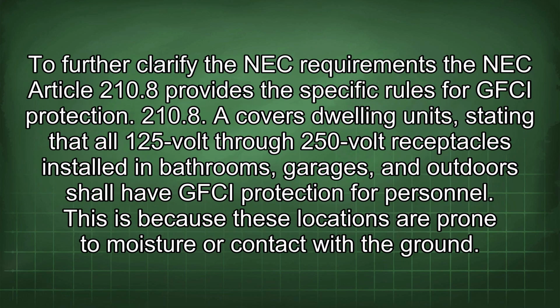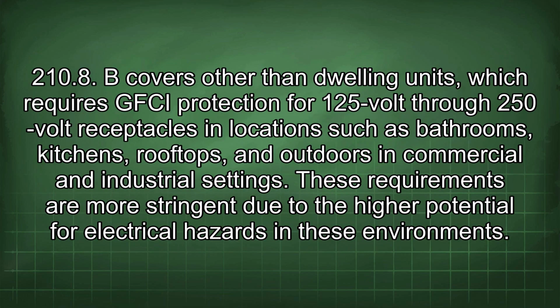To further clarify the NEC requirements, the NEC Article 210.8 provides the specific rules for GFCI protection. 210.8 A covers dwelling units, stating that all 125 volt through 250 volt receptacles installed in bathrooms, garages, and outdoors shall have GFCI protection for personnel. This is because these locations are prone to moisture or contact with the ground.